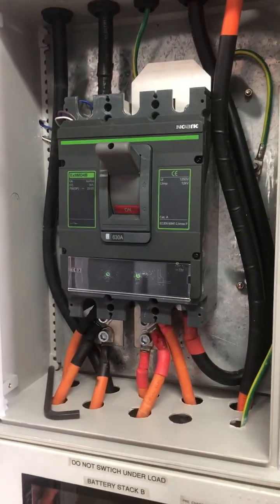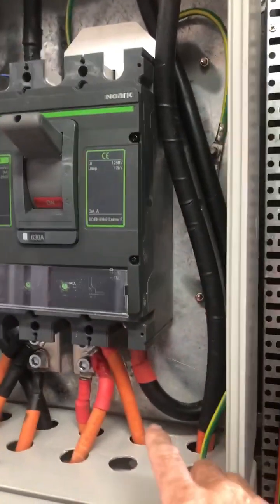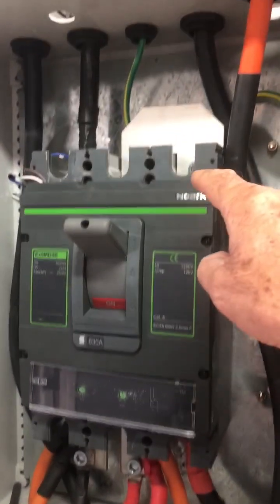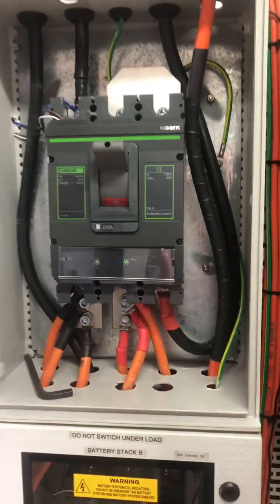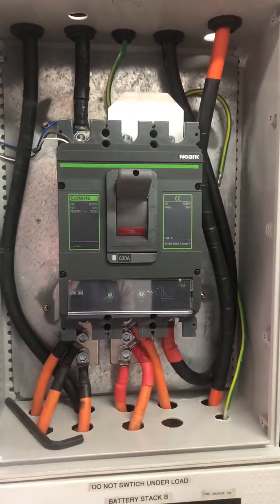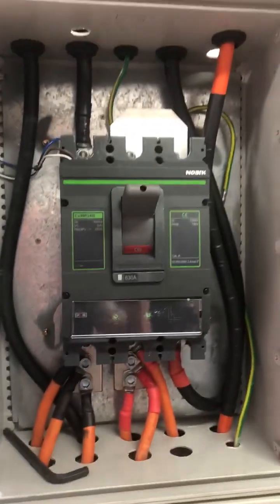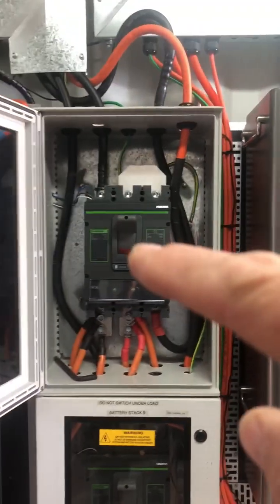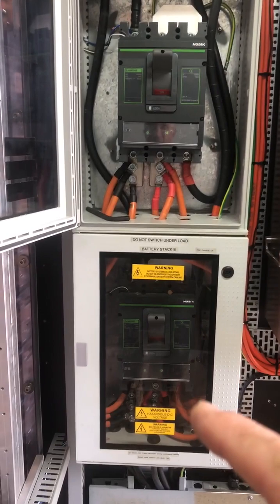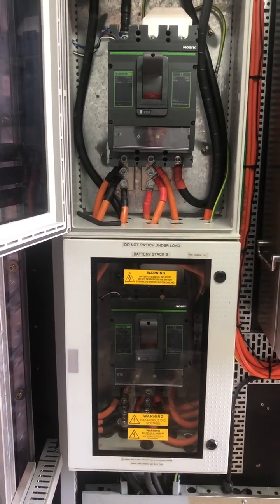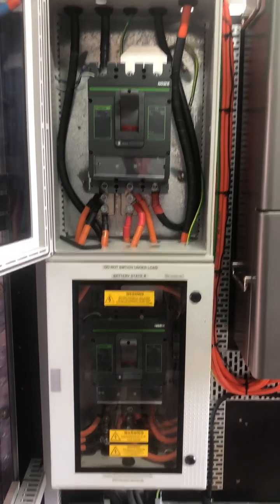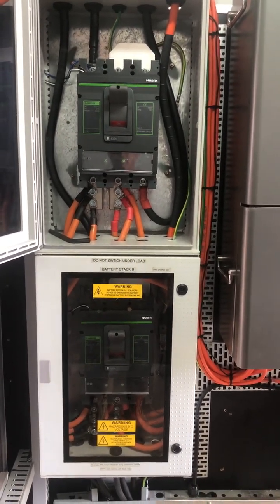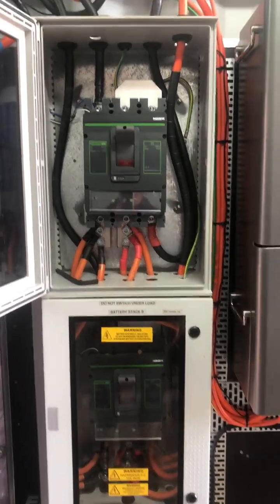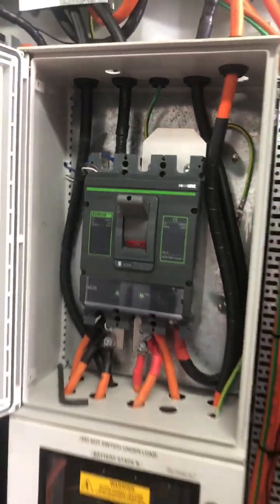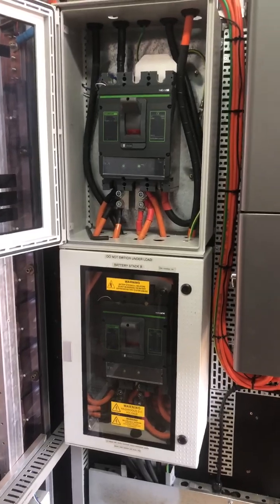Interestingly, these type of DC circuit breakers are designed so that the positive comes in one side, goes up, goes across, and comes out, as part of the design to be able to operate at the full 630 amps if required. Then this DC isolator also links on the load side of the isolator down the bottom here, so that they're all actually part of the same DC bus. However, on the line side, meaning the battery side, each isolator goes to a different battery stack.